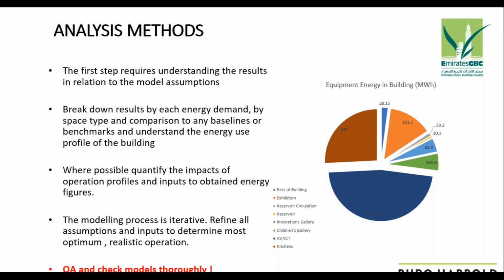If you look at this pie chart, it explains what I'm talking about. For this building we did the energy model for, the big blue slice is AV/IT loads, and the next big brown slice is from kitchens. So already we could tell most of the load came from AV/IT and kitchens. When we further analyzed that AV/IT load, we realized the reason we were getting such huge loads was because we were simulating them at 100% for the whole year. So we had to go through a process of understanding diversities, trying to apply sensible diversities, some of which were based on the experience of people who had worked in the field for a long time.